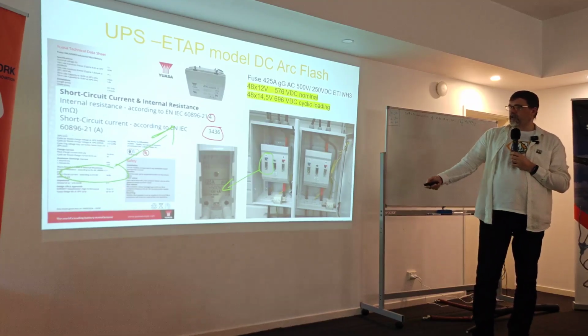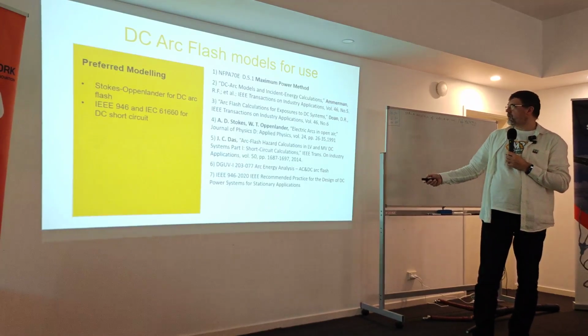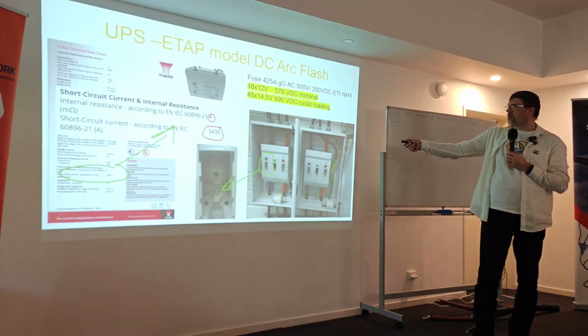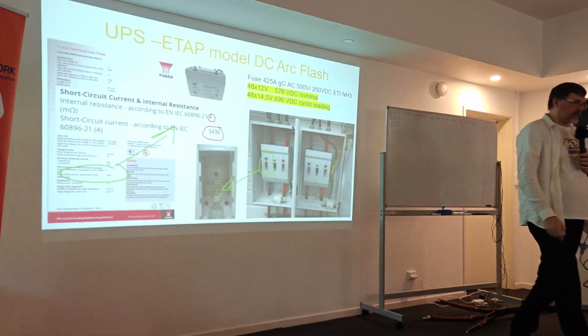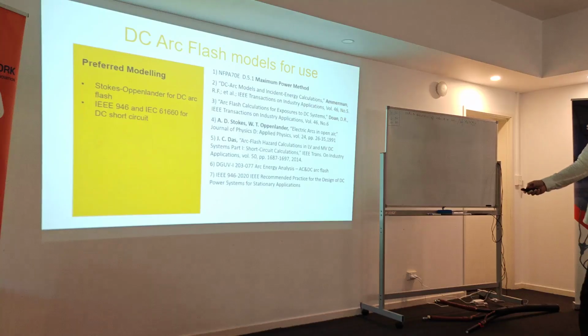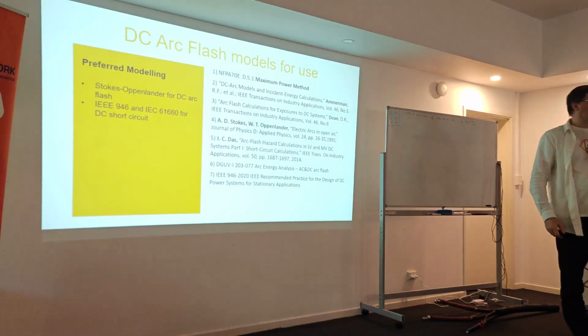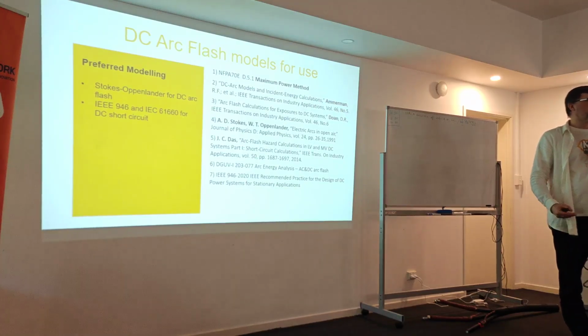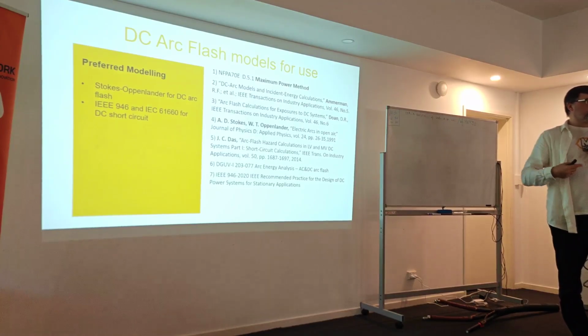Yeah. So we have this. We find out the short circuit current. We know we have an internal impedance. We know the voltage will vary because of the loading. On the batteries, speaking, is very hard. You will not keep the battery loaded, like they keep 20% charge, 50% charge for storage. You cannot discharge batteries fully. This is the tricky thing on the DC system, on the battery system, that you will never discharge it fully, because you can discharge it, but it's like 30 minutes, and then you have to charge them back.